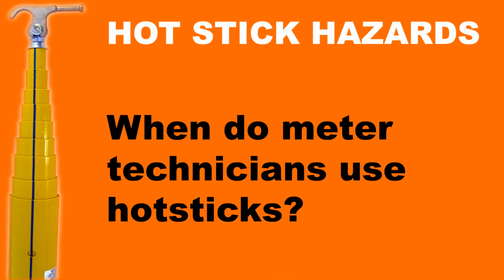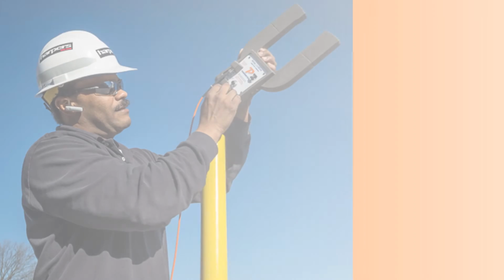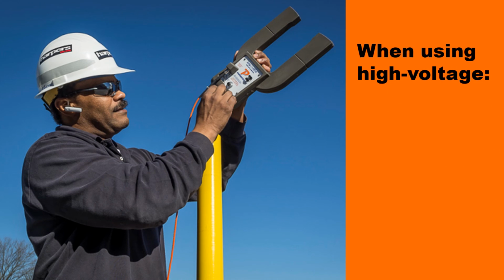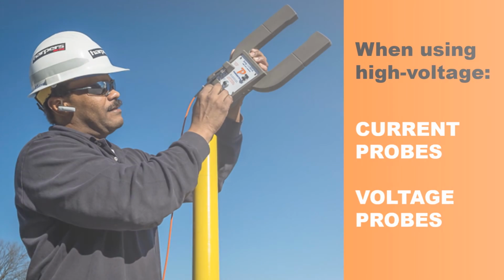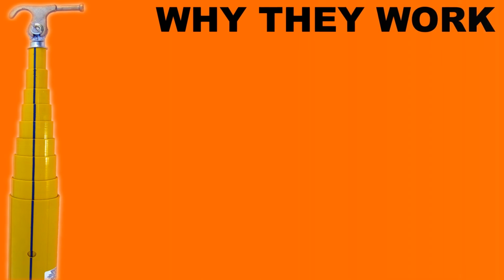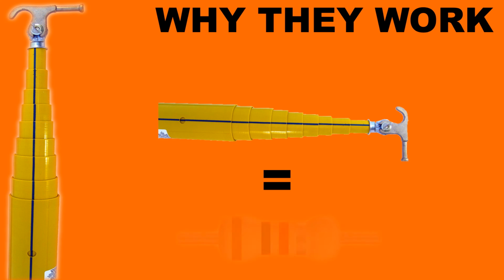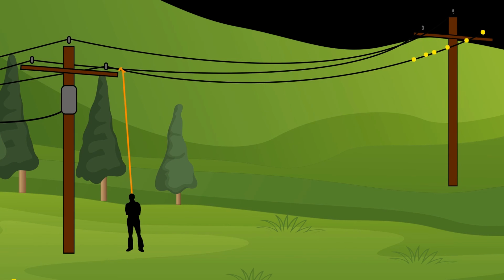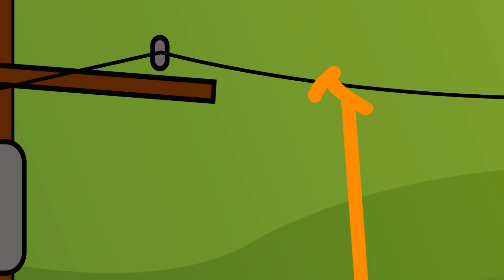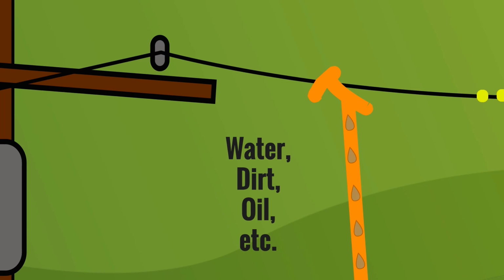Hot sticks also represent a significant hazard area for meter technicians when using high voltage current probes and voltage probes to test CTs and PTs at the transmission and substation levels. Hot sticks work because they're basically giant resistors that prevent the flow of electricity down to the meter technician. Usually the hot stick doesn't provide electricity with an attractive route to ground, but if your hot stick has dirt, oil, grease, water, or any other contaminant on it, current may find a path through these substances. It pays to keep your hot stick clean.